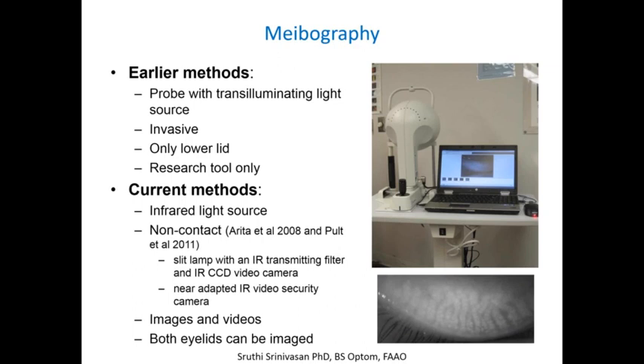Earlier methods of meibography were more invasive and meant to be a researcher's tool — mostly only lower lids could be imaged and it was quite invasive. Current methods normally use an infrared light source. There are other instruments besides the Keratograph 5 that offer meibography, including a slit lamp tool attached with an infrared transmitting filter and camera, and some researchers have adapted security cameras with infrared light for imaging meibomian glands. These devices can take images and videos of both upper and lower lids.